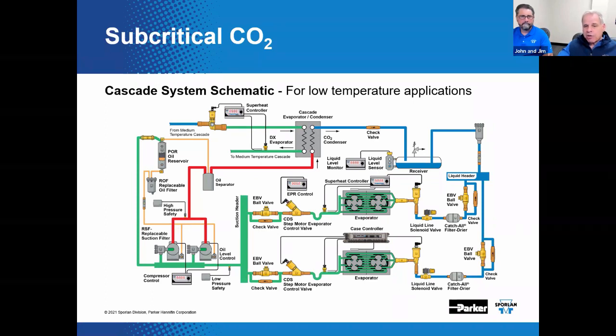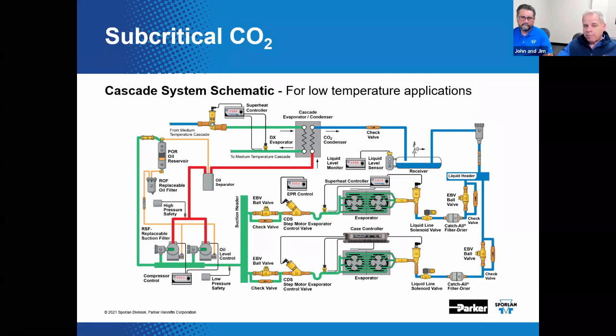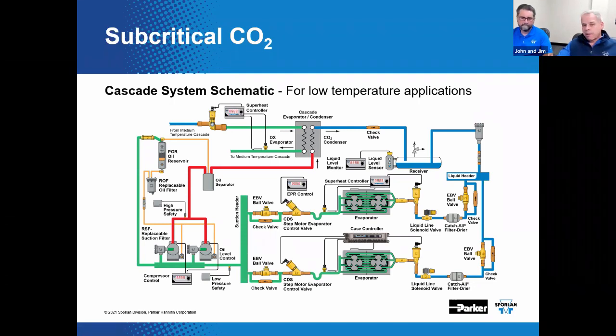Electrically actuated, electronically controlled valves are typically used on CO2 systems to handle the high required maximum rated pressure. What, 1,000 PSI, give or take? Yeah, a lot of times you're up to, I believe that's about 90 bar? Yeah, I believe so. And high maximum operating pressure differential, we've got a 580 PSID that we've got to withstand. That's right. Operating differential is a big deal on these valves as well.